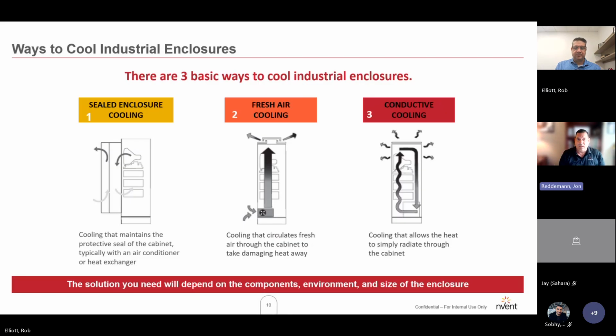Sure. And with the sealed enclosure systems, we have an air-to-air heat exchanger, which is also passive. The only difference between the air-to-air heat exchanger and the fresh air fan filter system is that we are recirculating enclosure air and we're keeping the enclosure sealed, as compared to pushing air through the enclosure. So if we have highly contaminated air, but it's at a good temperature, we would use an air-to-air heat exchanger and keep the enclosure internal sealed up, so we're not pushing those contaminants into the box.